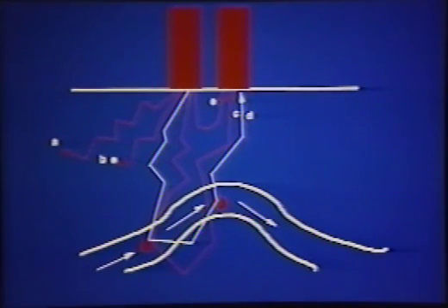Now, according to that approach, a photon could experience various fates once it reaches the tissue. From this transmitting fiber, much of the light would simply be scattered away and lost forever. Some would be optically absorbed. But the two components of particular interest are the light that's interacted simply with static tissue elements and actually made it back to the receiving fiber. Similarly, the very small fraction of that that's interacted with one or more moving red blood cells and experienced Doppler shifts. So it's these two types of light then that at the photodetector should set up beat frequencies.